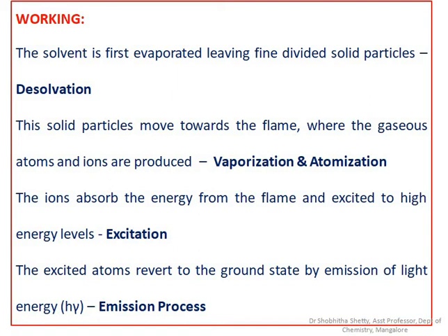Once they reach the higher energy level, they are no longer stable there for a longer period, so they revert back to the ground state by emitting the excess light energy that they have absorbed. This process we call the emission process. Based on the amount of light radiation emitted, as well as the nature of the light radiation emitted, we can find out the nature of the element as well as the concentration of the element present. So mainly desolvation, vaporization followed by atomization, excitation and emission process.